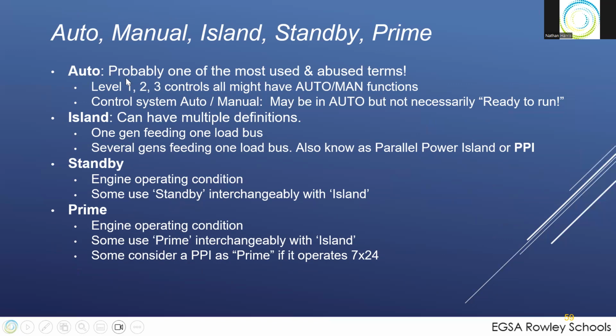And the thing I don't like about the term auto, and it's probably one of the most abused terms out there, is you can actually be in auto and not ready to run. I feel that if for some reason you're not ready to run, you should force yourself not to be in auto anymore. But some systems actually can be left in auto and have a signal that's required by NFPA and the standards to signal if your system's in auto or not. So you leave your system in auto, but it still may not work. So you have to be careful of that term.